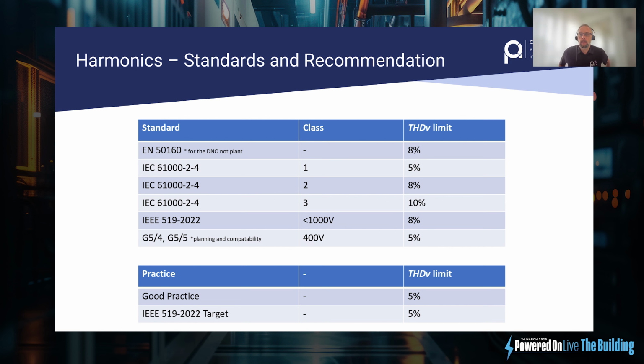So we have some standards. These are just some examples, to try and prevent equipment that's being installed causing more problems. And the design of this is really to make sure that A, your transformer's okay, the best possible it can be, and that you don't impact, or the factory doesn't impact, the connection upstream into the grid, which ultimately means they don't affect their neighbor as well. The standards don't really protect the facility. There's a lot of bandwidth in there. So these aren't things you're aiming for. You're trying to avoid getting this high, basically.